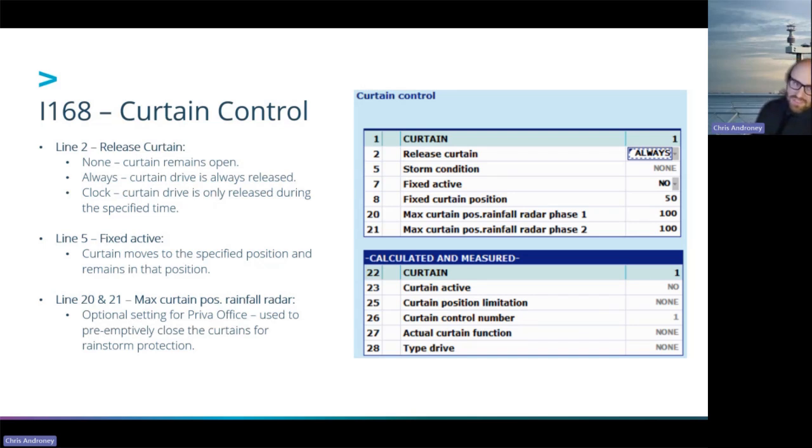One thing to keep in mind when you're using that fixed active, if it's something that you're just going to temporarily override the setting, I would suggest to use the temporary settings, because once you have it set to fixed active and you turn that to yes, the curtain's going to go to whatever position you have in there and it's going to stay in that position. So even if one of the strategies is asking, say your energy strategy is asking for those curtains to close, if you have fixed active set to yes, the curtain's going to stay at whatever position you put there.